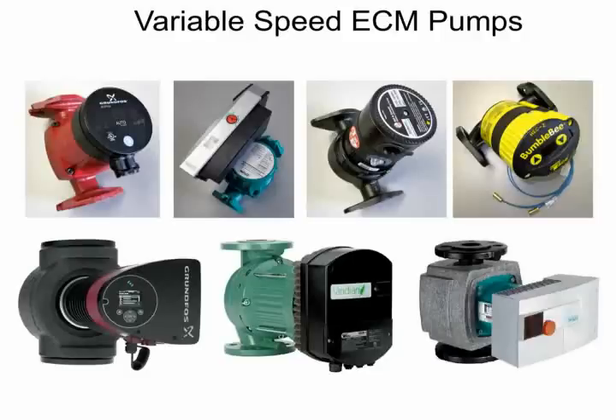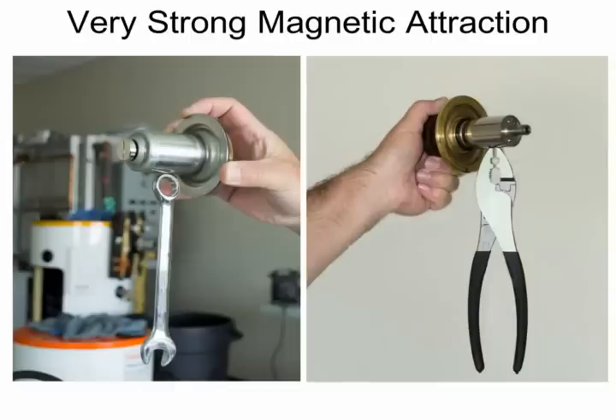So ECM motors are very common. Xylem and Grundfos and Taco and Wilo, probably just to name some of them that are in the market, are out there, very good pumps. But what they have in common is they use permanent magnets in the rotor. In the wet rotor, there is a permanent magnet. Rather than inducing a magnetic field into the rotor, the magnet's already there and allows pump manufacturers to get very high efficiency, for lack of better words, if you will.